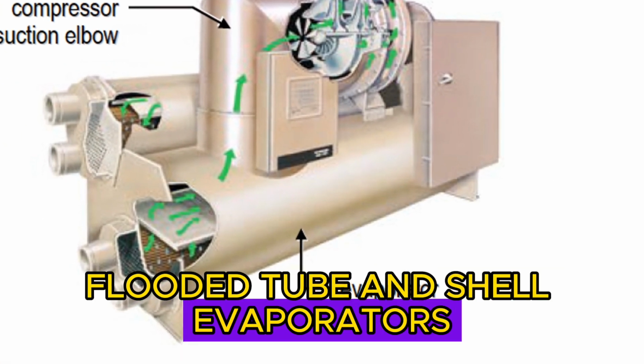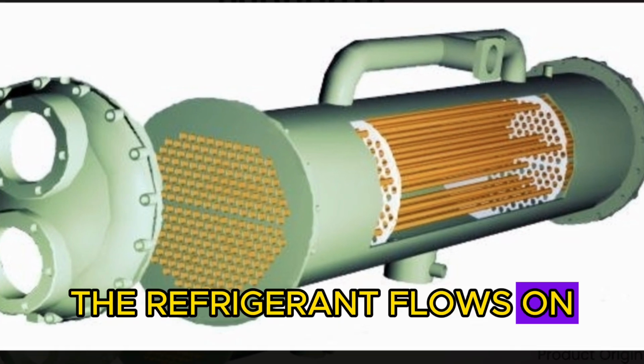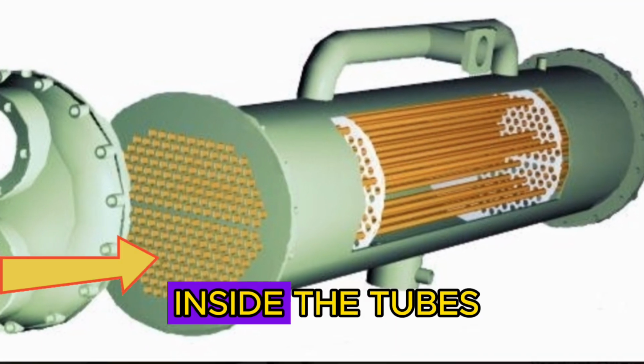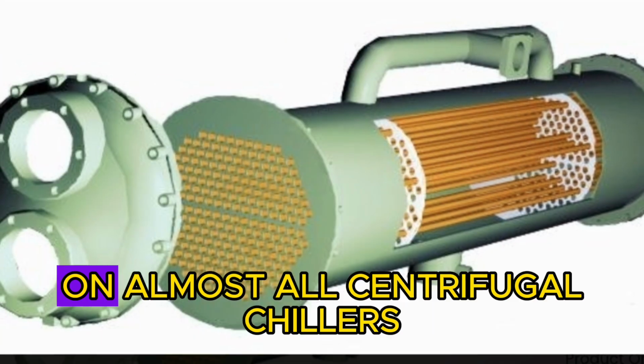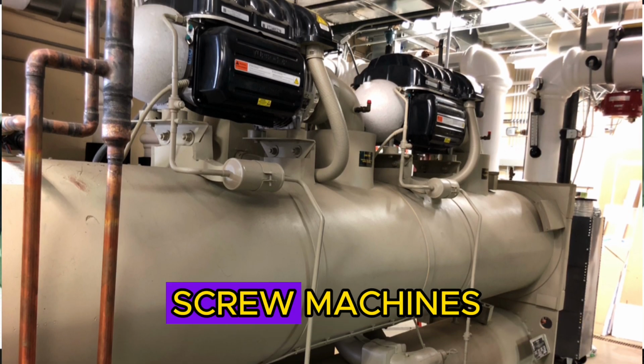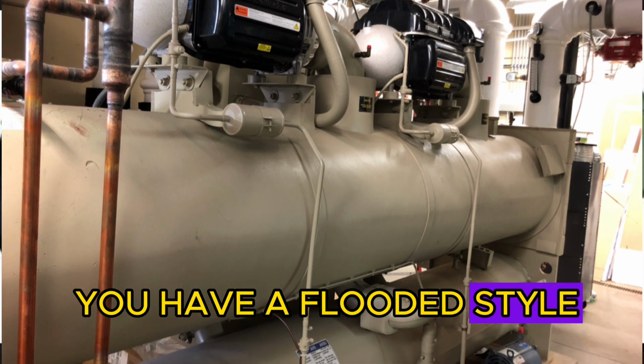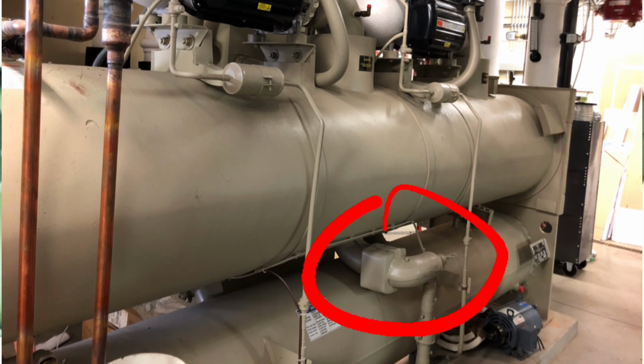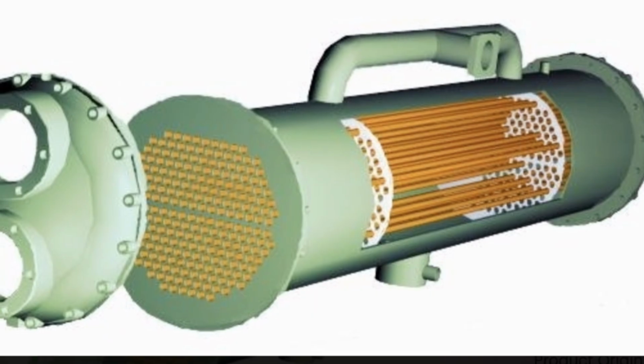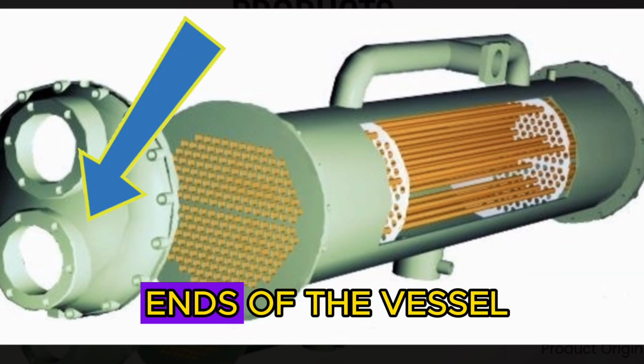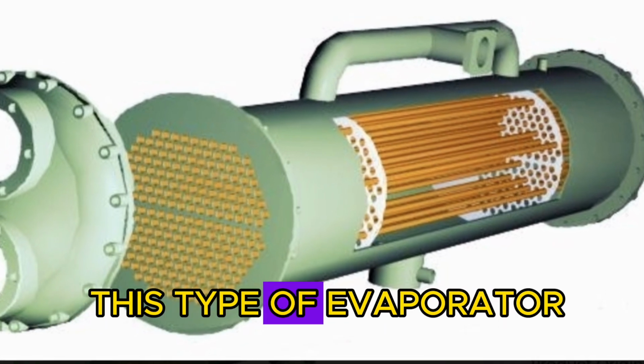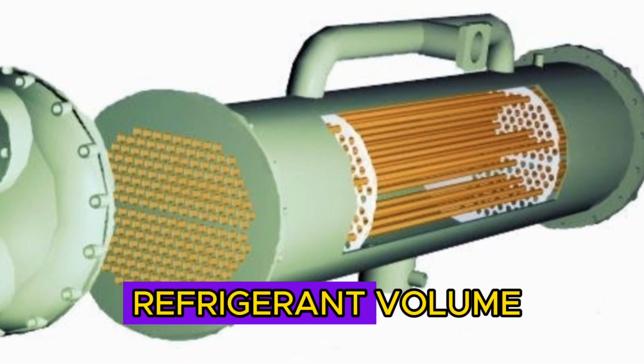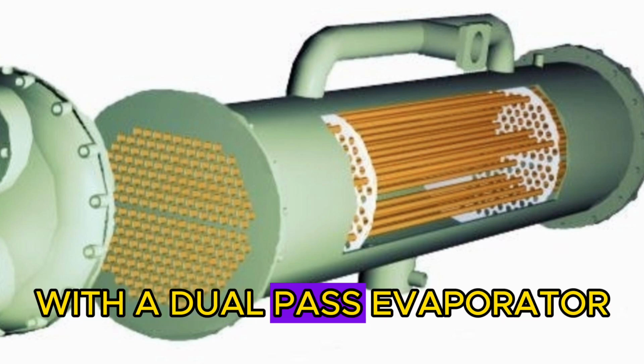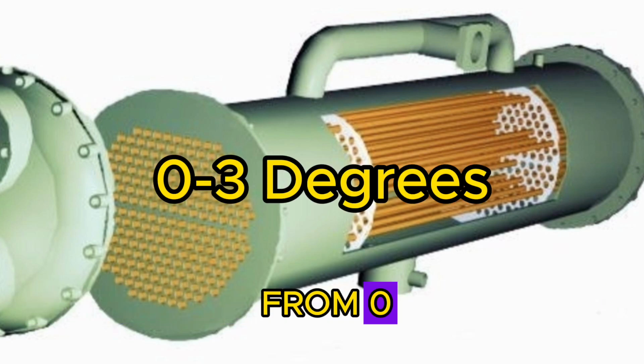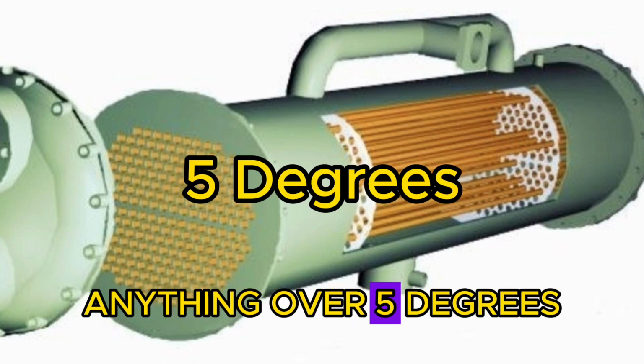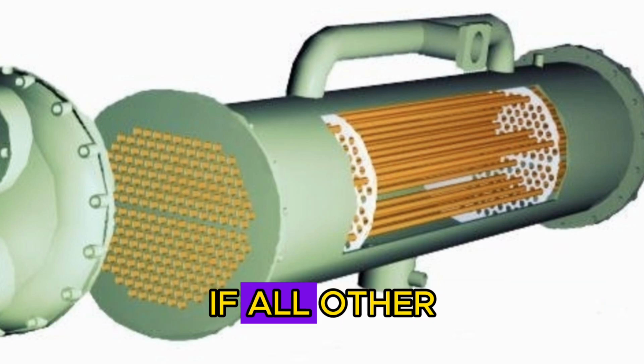Flooded tube and shell evaporators. In a flooded evaporator, the refrigerant flows on the outside of the tubes and the water flows inside the tubes, hence the name. This is very common on almost all centrifugal chillers, as well as some screw machines. You can tell if you have a flooded style evaporator because the expansion valve feeds into the center of the vessel at the bottom. The water on these evaporators typically enters at the ends of the vessel. The design approach for this type of evaporator is quite a bit lower due to the larger refrigerant volume and greater efficiency. With a dual-pass evaporator, the design approach ranges from 0 to 3 degrees Fahrenheit. Anything over 5 degrees would require a shutdown for tube cleaning if all other readings are correct.